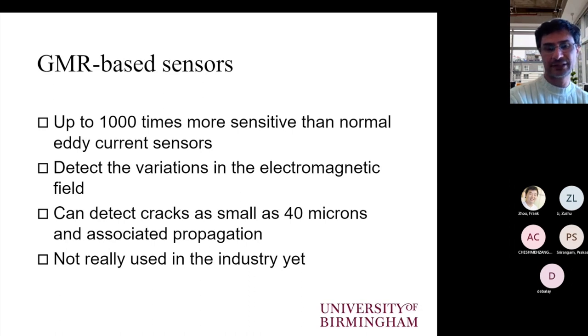As I said, in industrial instruments, it is always a coil that is used instead, or in very rare cases, Hall probes. So GMRs are predominantly at the moment restricted to experimental configurations, which are not as of yet used by the industry, even though GMRs have been around for a good 20 years plus, but with limited industrial application. However, this can potentially increase the sensitivity of eddy current testing to very, very small levels, and potentially even enabling them to detect increments of crack growth. Of course, in conventional eddy current testing, the sensitivity, or the resolution, if you prefer, is related to the size of the coil.